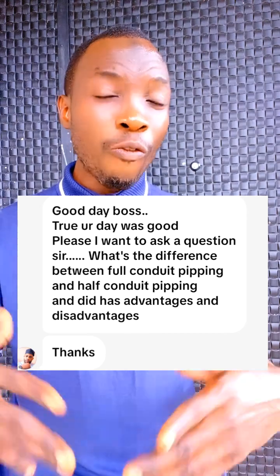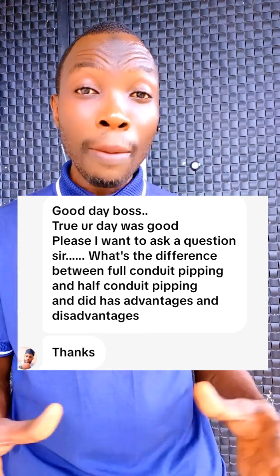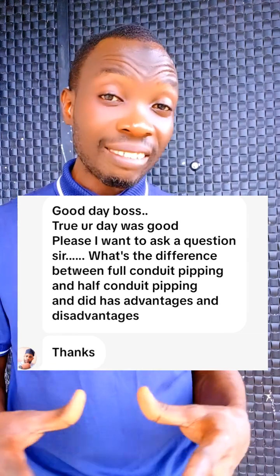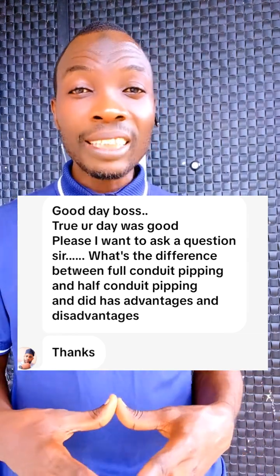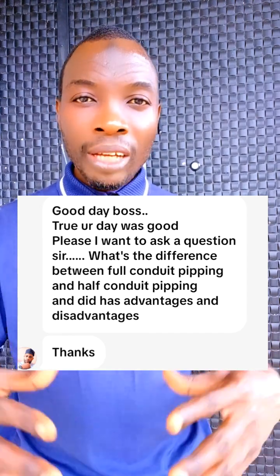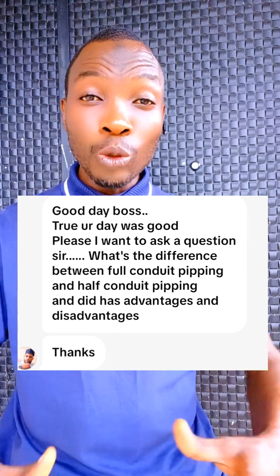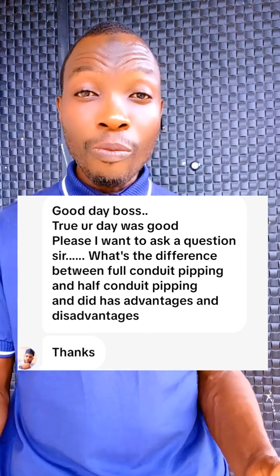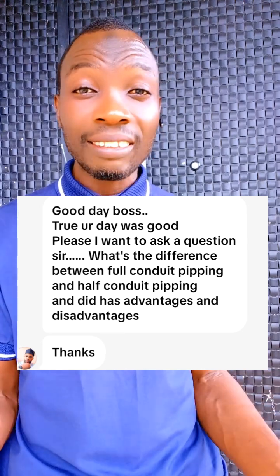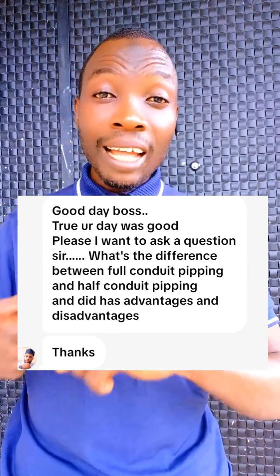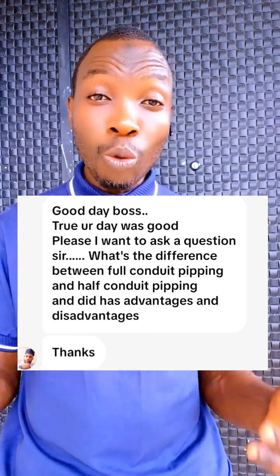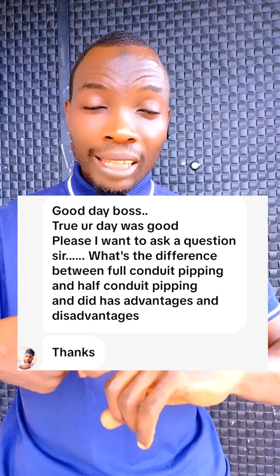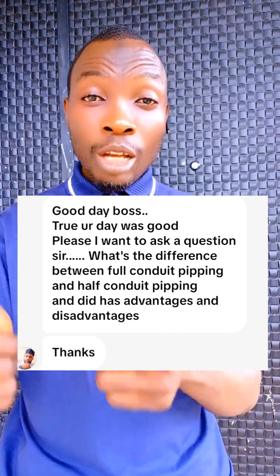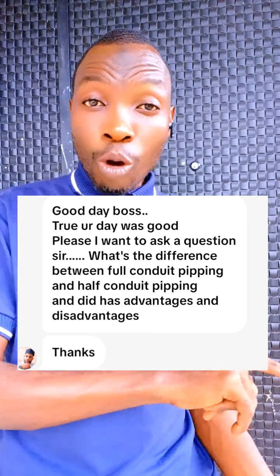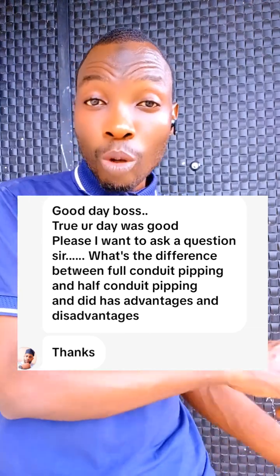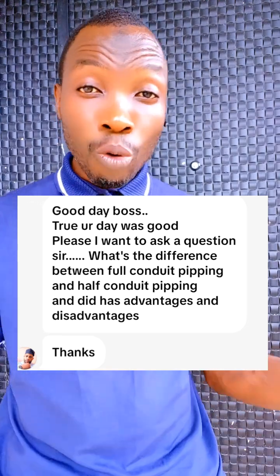Another advantage of full conduit over half conduit, apart from rodent attack, which I cited just now, is that during maintenance, if a cable gets burnt or you want to change a cable in the installation to a bigger size, from one end, attach a new cable to the one you want to replace, and go to the other end and draw it out. As the old cable goes out, the new cable comes in with it, if it is a full conduit.